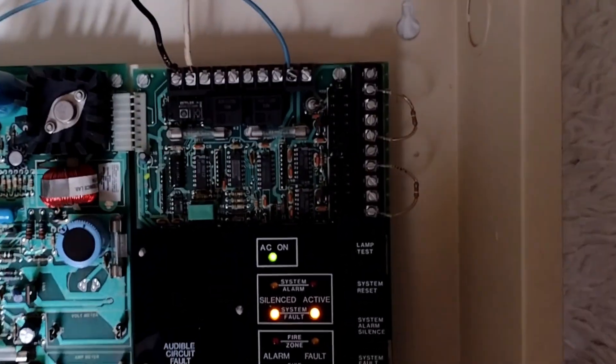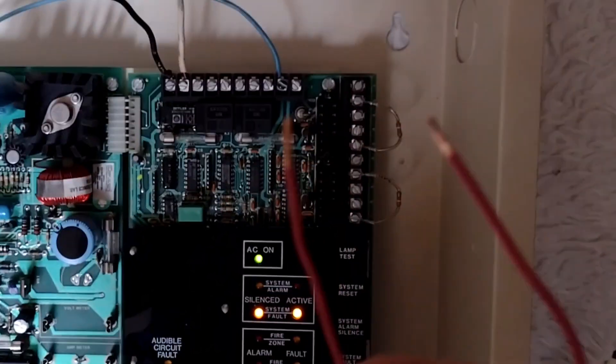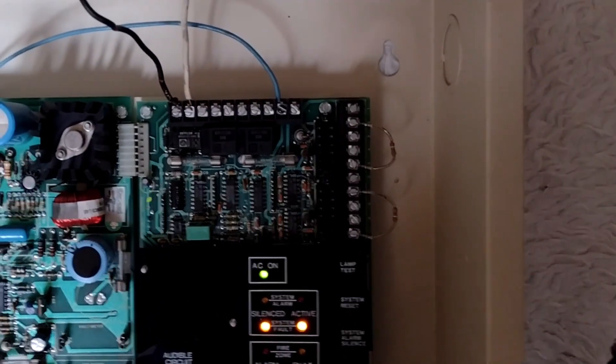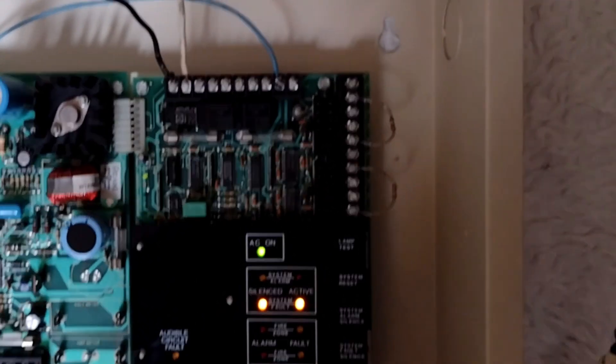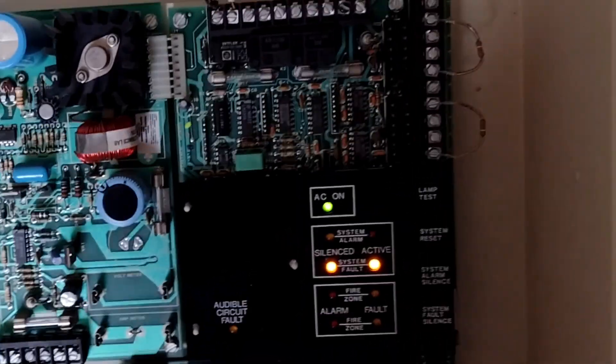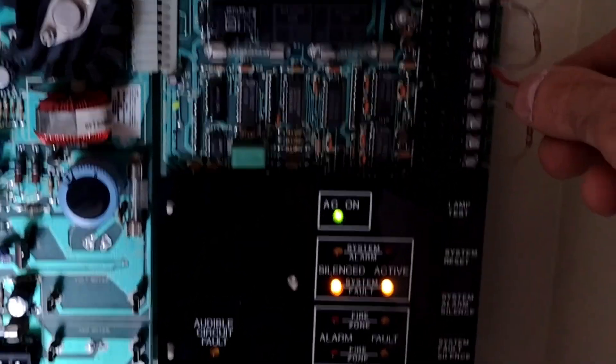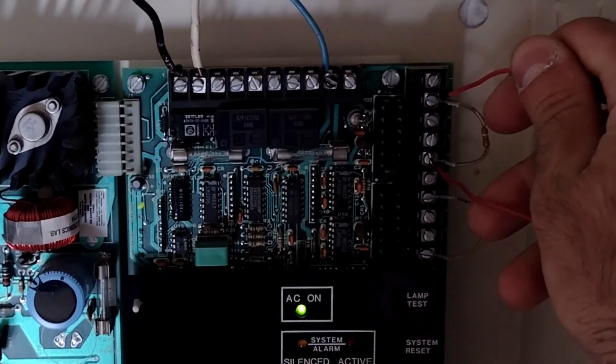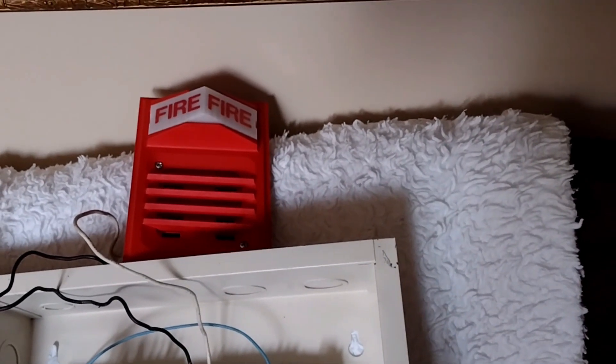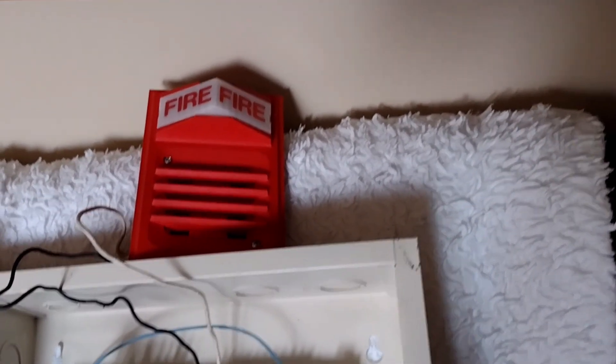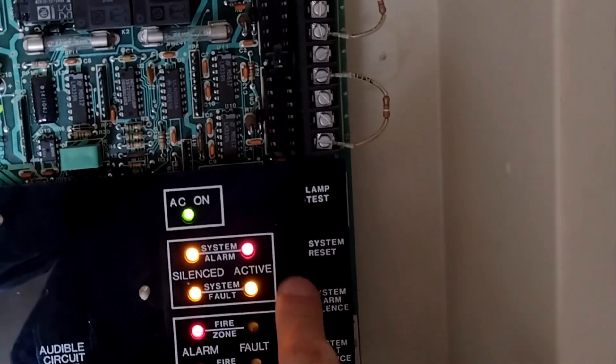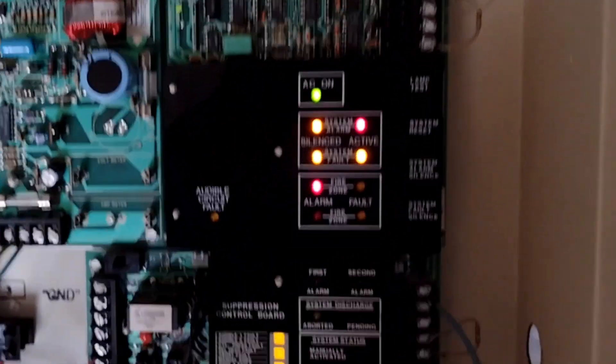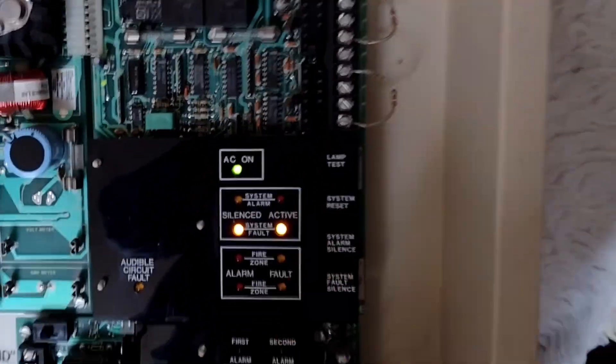So the first one is a general fire alarm. I'm going to be using this jumper to just short out the terminals because I didn't feel like wiring three separate initiating devices up. I'm just going to show you how this works. So we're going to cause a general fire alarm. Maybe this is their monthly fire drill in this tiny office complex. I'm just going to silence the system. That switch is a little sensitive. Now we're going to reset. We'll let everyone back inside.